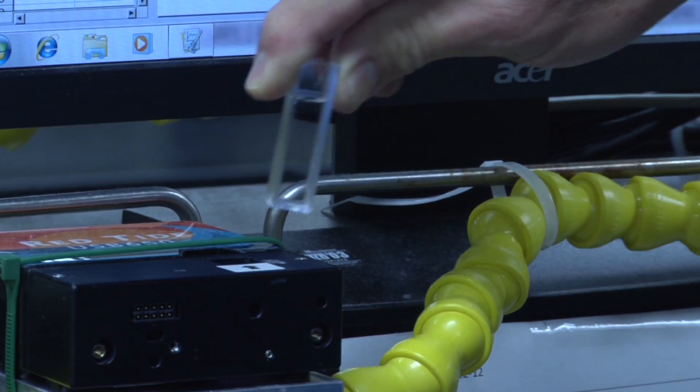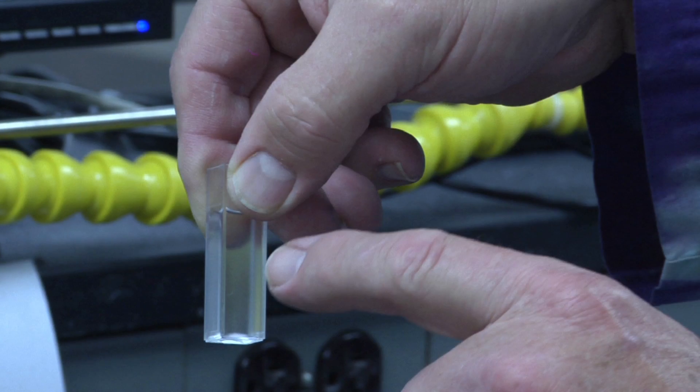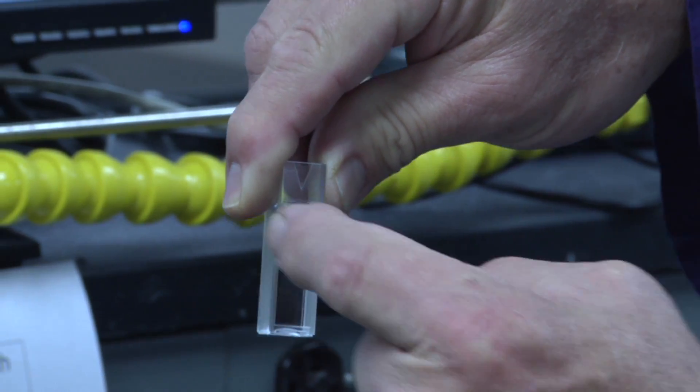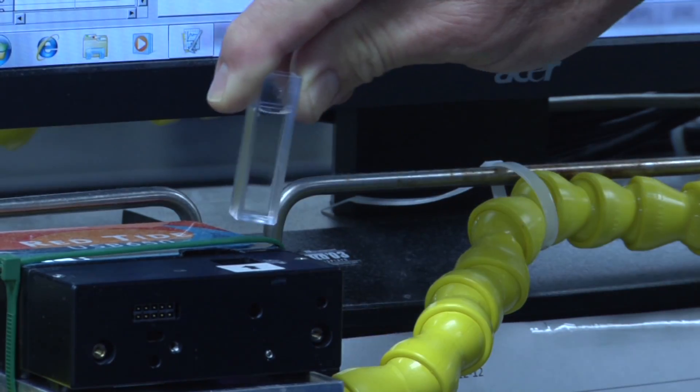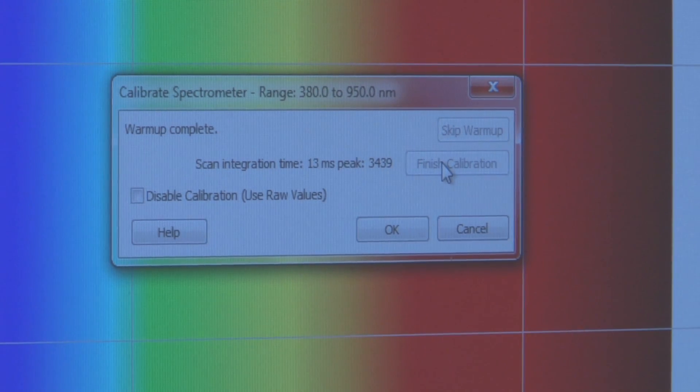Next you will need to finish the calibration with the cuvette containing pure water in the cell holder. Notice that the cuvette has clear sides and frosted sides. Make sure the clear sides line up with the light path as indicated on the holder. With this reference cuvette in place, select the finish calibration button.